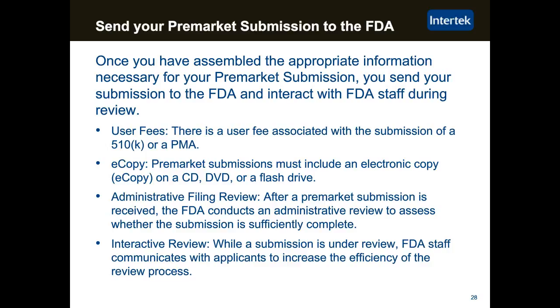You will have to pay some user fees. There's a user fee associated with the submission of both the 510K and the PMA, and I'll cover that in a subsequent slide. You also need to format the materials as what they consider e-copy, and there are guidelines on the FDA website on how that needs to be handled. So they're looking for electronic submission in addition to any paper submission.